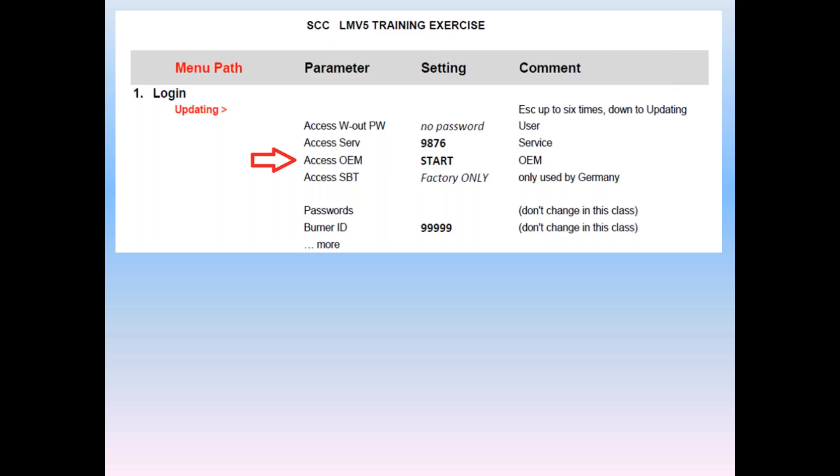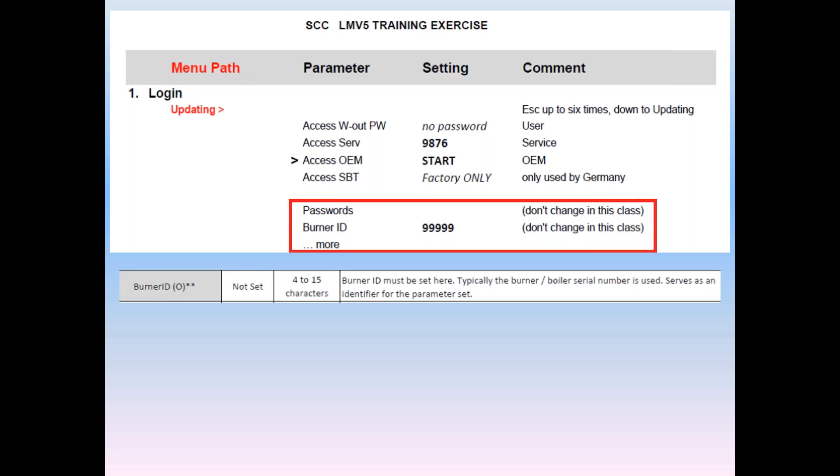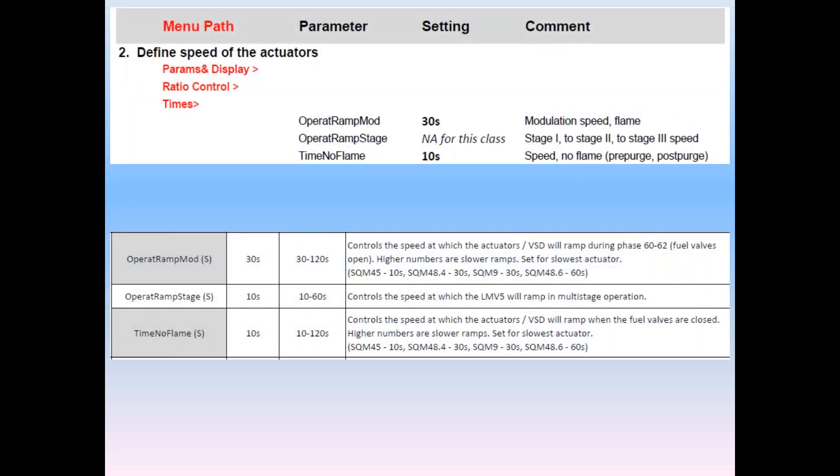Every unit must have a burner ID in order to run. The burner ID has to be between 4 and 15 characters and there is no default. Best practice is for each unit to have a different ID. Much of the configuration is completed while the LMV5 is, in fact, in the thick of an error, such as no fuel train. No worries, we just press escape and continue to set the unit up. Resetting the fault will not help until the settings are corrected. So, let's go on to number two and define the speed of the actuators.